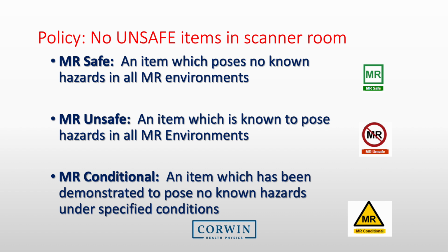An MR conditional label device is one that has been demonstrated to pose no known hazards under specific conditions. The documentation with these devices must be reviewed and evaluated to ensure the MR conditional device can be brought into the MRI room. For instance, some items may be labeled conditional and specified that they have been evaluated and found safe in a 1.5 T magnet room. This would mean that the item has not been found safe to be within an MRI room that is a 3T system.